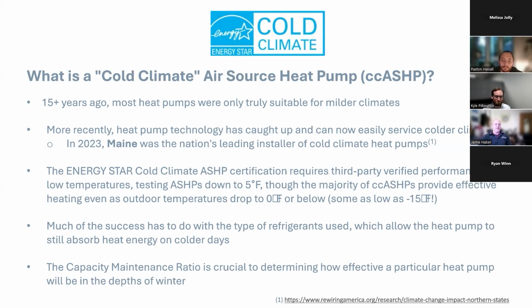The majority of cold climate air source heat pumps provide effective heating even as outdoor temperature drops to zero. Some are even tested below zero. I've seen tests at -13, -15, and these systems are still putting out 60 to 70% of their capacity at -15. That's ridiculously good, because the number of hours a year that temperature is actually realized is very, very small. So you can feel comfortable that if it's cold climate rated and has the good statistics we were talking about, the good capacity maintenance and whatnot, you'll be just fine.